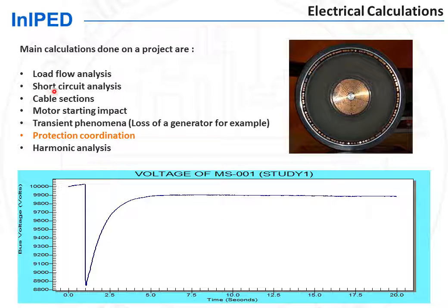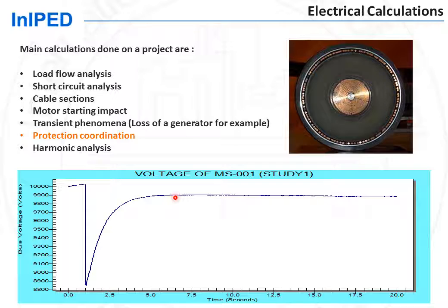Besides the calculations already mentioned for the electrical system, the electrical engineer performs cable cross-section calculations as well as transient analysis — for instance, the loss of one of the main power generators. The purpose is to check that the voltage dip is not deep and long enough to affect the process, for instance to cause the large process pumps to stop.